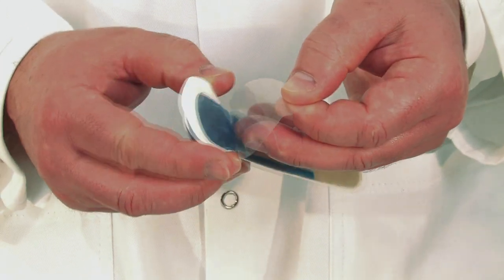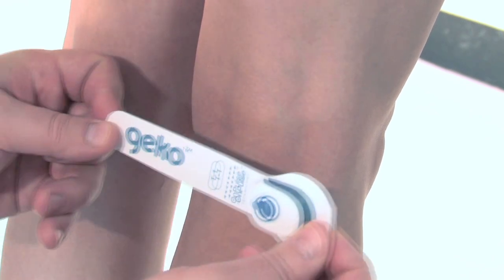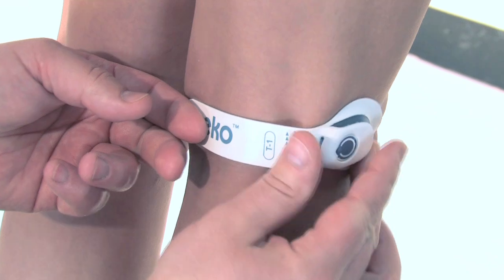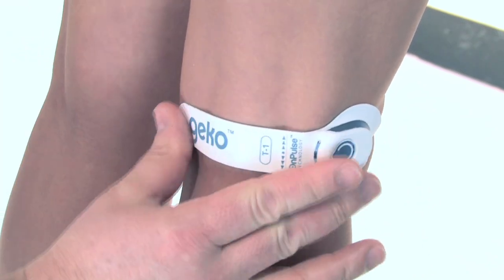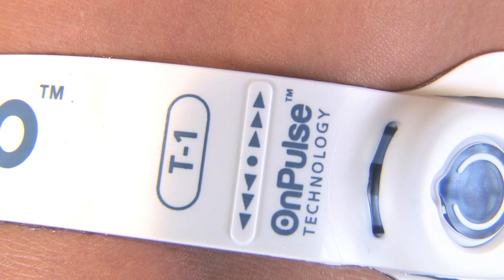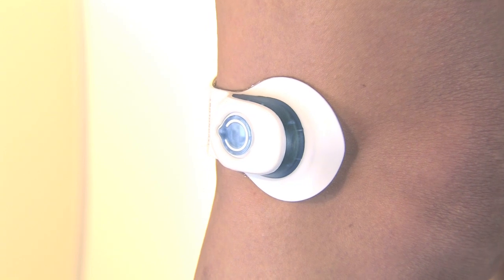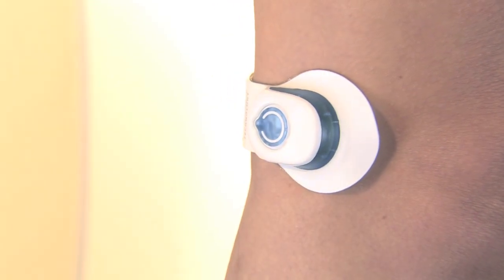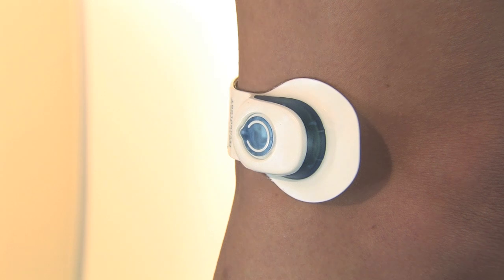With the device switched off, peel off the disposable backing film, then position it behind the knee, above the crease, with the lower edge of the device very slightly touching the crease, and the control button to the outside of the leg. There is a raised indicator line marked with arrows on the back of the device, which should be aligned with the outer tendon. This will ensure that the electrodes are positioned correctly above and in relation to the common peroneal nerve. Once in position, use one short click of the button to activate the geko device. The LED will flash regularly every one and a half seconds to signal that it is operating correctly, and that the lowest level of stimulation is selected.